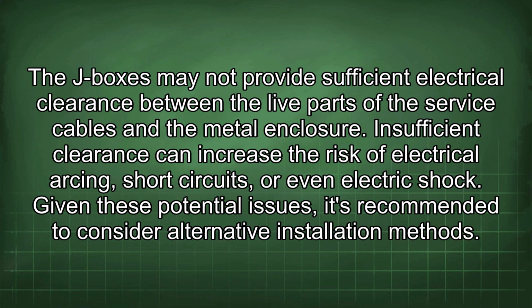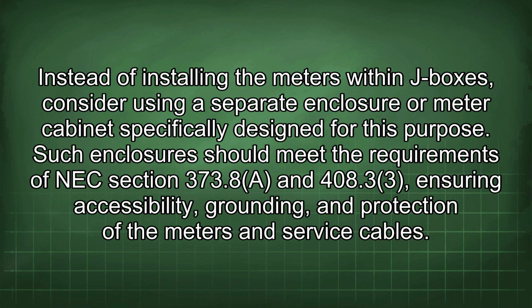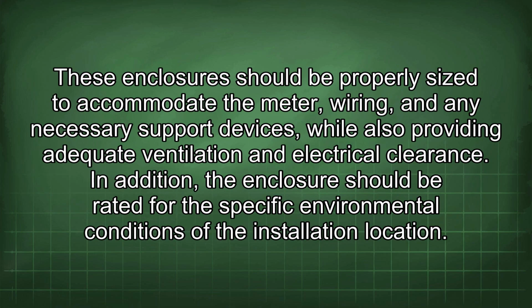Given these potential issues, it's recommended to consider alternative installation methods. Instead of installing the meters within J-boxes, consider using a separate enclosure or meter cabinet specifically designed for this purpose. Such enclosures should meet the requirements of NEC Section 373.8(A) and 408.3(3), ensuring accessibility, grounding, and protection of the meters and service cables. These enclosures should be properly sized to accommodate the meter, wiring, and any necessary support devices, while also providing adequate ventilation and electrical clearance. In addition, the enclosure should be rated for the specific environmental conditions of the installation location.